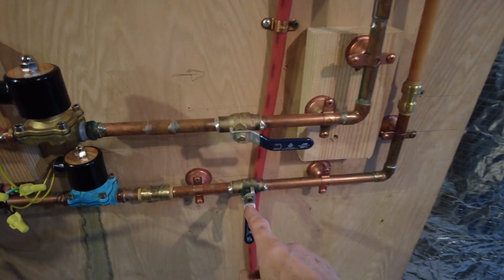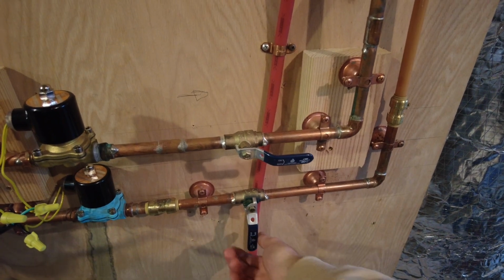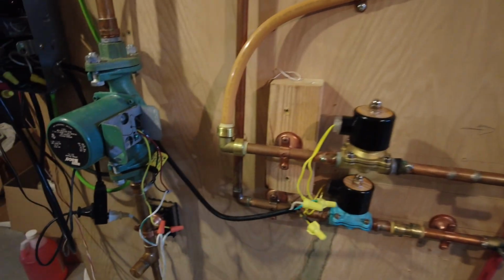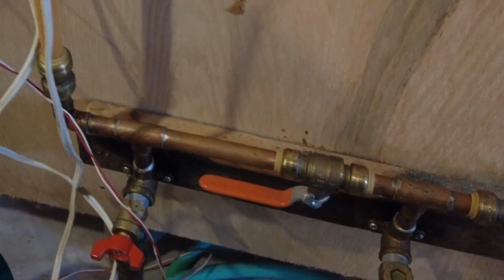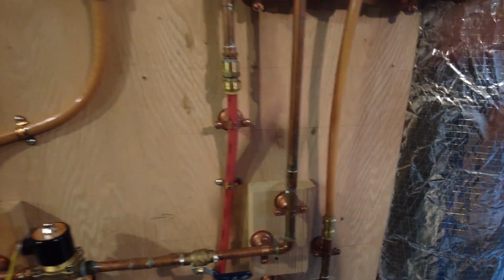Again, this is the thing you have to remember - this is how I blew the other one off. You've got to make sure you check all your valves to make sure it's in the right operation. These two need to be closed. This is my main circulation valve. These are the isolation valves for the solar and the chimney kit.